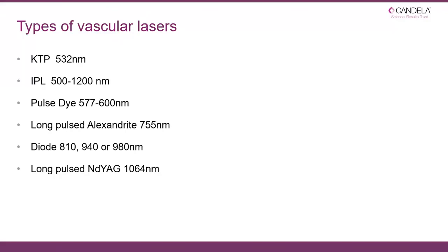And that was determined after a great deal of studies, putting systems into different clinics and seeing which was the most efficient wavelength, and we found that 595 gave the best compromise between absorption into hemoglobin and depth of penetration.